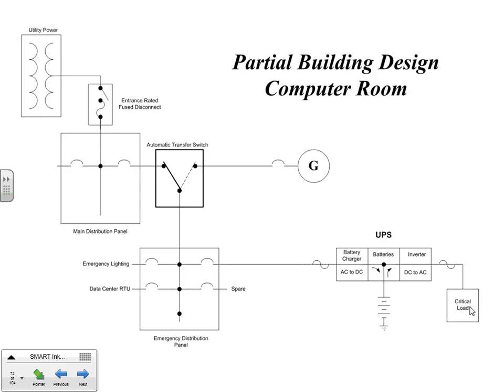In this scenario, we see the UPS we just talked about, providing power to the critical load, sitting over here. That's in distribution. And in this scenario, this is actually our emergency distribution panel because it's downstream of our transfer switch. It looks like we've got some spares here. We've got a data center RTU, so we've got our air conditioner for the data center room, the UPS room. And we've got some emergency lighting.